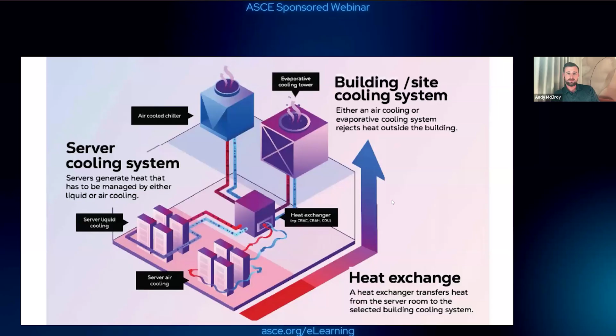As the workloads in data centers have increased, so has the heat, and this air-to-water cooling is no longer sufficient to support the densities inside these buildings. So they've added a secondary cooling network, which you could call a CDU, a coolant distribution unit. They could look a few different ways, but we'll use the CDU example. It does essentially what the air-cooled chillers on the roof are doing, but takes cold liquid in a lot of cases directly to the chip via what's called a cold plate. They remove about 60 to 70% of the heat generated by a server directly at the chip level, then deliver that hot water, making hot air out of it, and put it into a contained aisle to be removed by that primary legacy system.